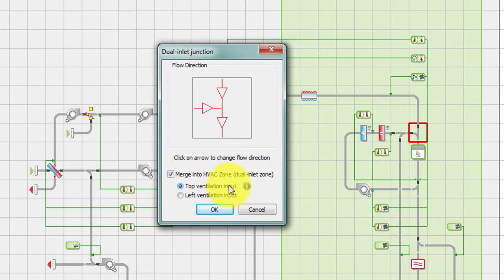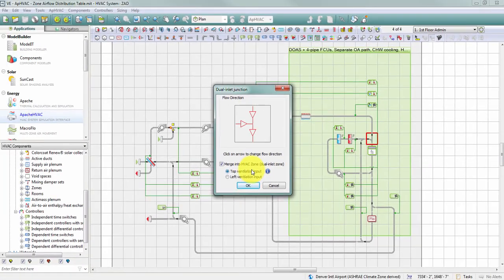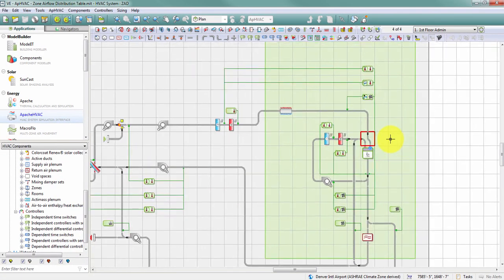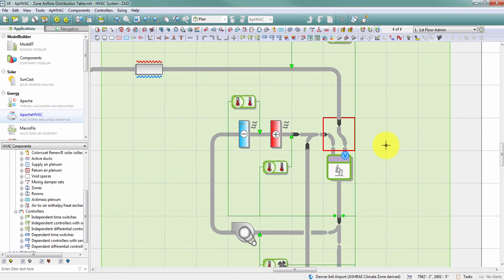For this prototype system, top ventilation makes the most sense since ventilation air comes from the top and the recirculated path through the fan coil unit comes from the left. After clicking OK, a dual inlet zone is created. The blue V confirms which path the software identifies as the ventilation path — in this case, the top branch.